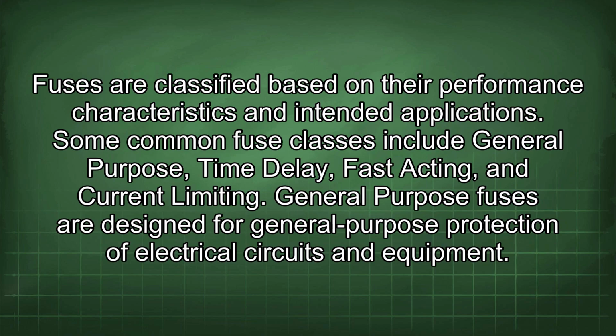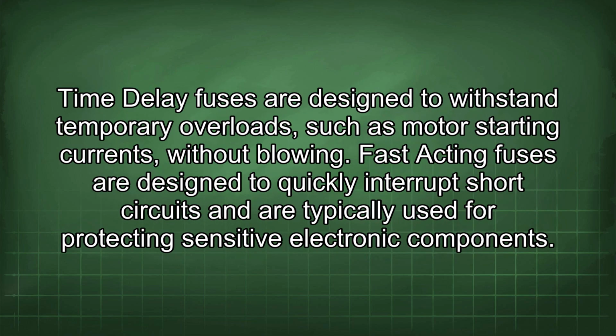Fuses are classified based on their performance characteristics and intended applications. Some common fuse classes include general-purpose, time delay, fast-acting, and current limiting. General-purpose fuses are designed for general-purpose protection of electrical circuits and equipment. Time delay fuses are designed to withstand temporary overloads, such as motor starting currents, without blowing.